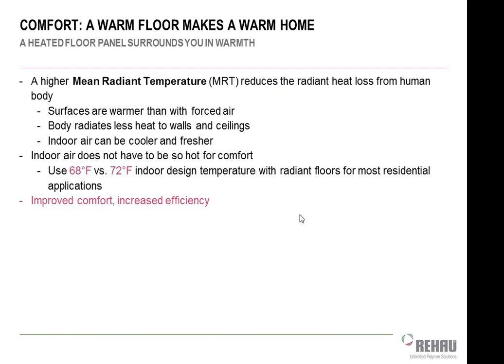So usually, I mean, this is showing you 4 on this chart here, but usually it's going to be 6, 8 degrees lower temperature that the radiant floor user is going to set on his thermostat than the air side heating user is going to set. And obviously the lower temperature thermostat is going to reduce energy use. The lower the air temperature inside the space, the less the space is giving to the outdoors. The rate of heat transfer from inside the building to outside the building is based on the delta temperature between those two. So the closer the indoor temperature is to the cold outdoor temperature, the less heat transfers through the wall. So if I keep your space at 65 instead of at 75, I'm going to give less heat up to the outdoors, which means I need to run my boiler less, which is going to end up saving you money.